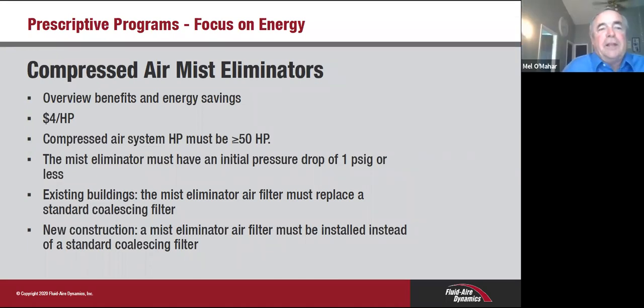All right, well, mist eliminators. Basically, a big reason for them is you can filter your air properly and get any contaminants out without having a large pressure drop. Most filters, or mainline filters, will have 4 to 5, sometimes 6 PSI of pressure drop across the system. And the key in energy savings is to try to keep your pressures as low as possible. And that's why you would put in a mist eliminator in lieu of, let's say, just a coalescing filter.